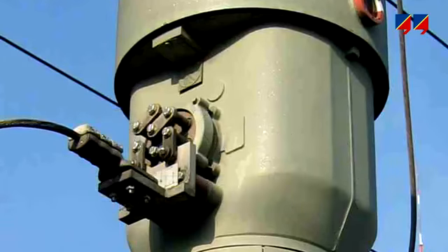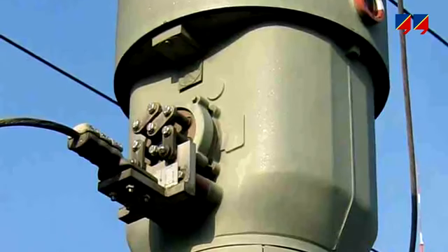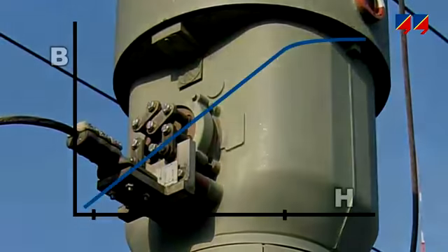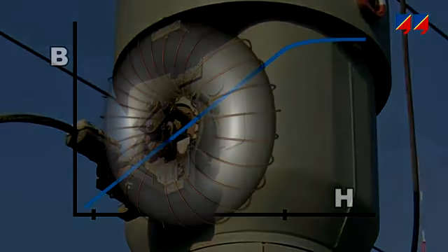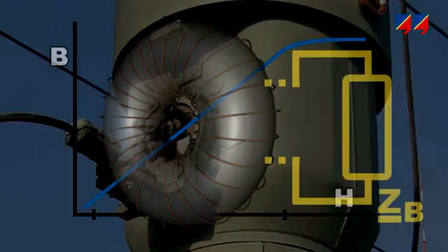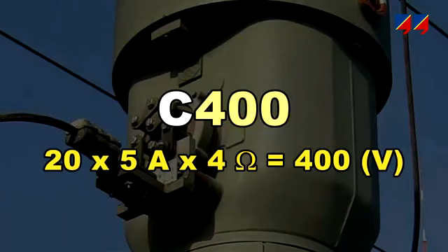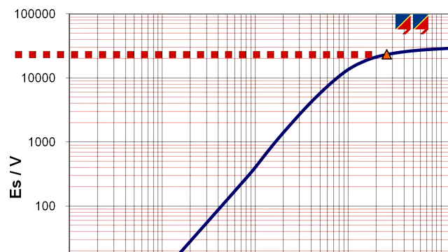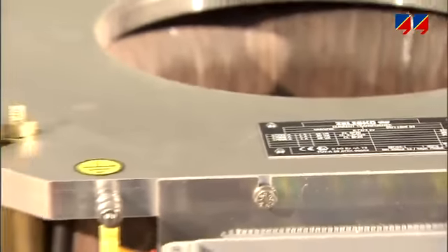C57.13, a similar approach is used by calculating the terminal voltage from the CT's excitation curve and considering its winding resistance and external burden. For example, the protection class C400 means that for a burden of 4 ohms and at 20 times the rated current, the CT must not produce an error of more than 10%. This requires high driving voltages, resulting in the need for large iron cores.